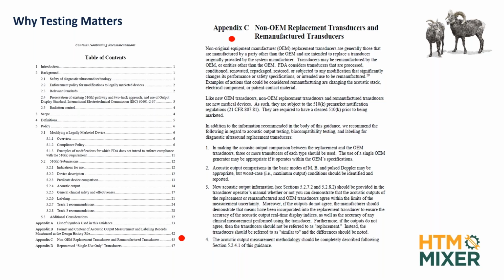But that doesn't mean it's right. It could have higher output power. It could have lower output power. Higher output power means there's a safety issue for the patient. Lower acoustic output power means there is a problem that the patient could run into. The probe is not working in its output. So you get misdiagnosis or underdiagnosis. Okay, all of these things have to be considered.